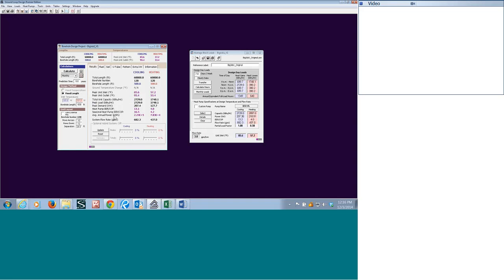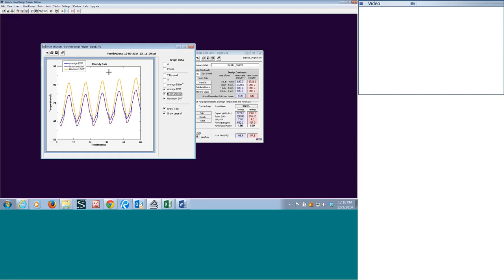But before we go on, I want to just show you what can happen just on spacing alone. If you'll notice at 5 years, we're predicting 85 degrees. I'm going to take this to 35-foot spacing, and I want you to keep this in mind as we go through the webinar. You'll notice that dropped a few degrees. If we look at this graph, it's also started to level off this potential heat creep. And of course, in theory, what it's doing is saying, okay, we're getting more area between the boreholes to disperse heat. So we're not compressing it as much between boreholes and having as much thermal interference.